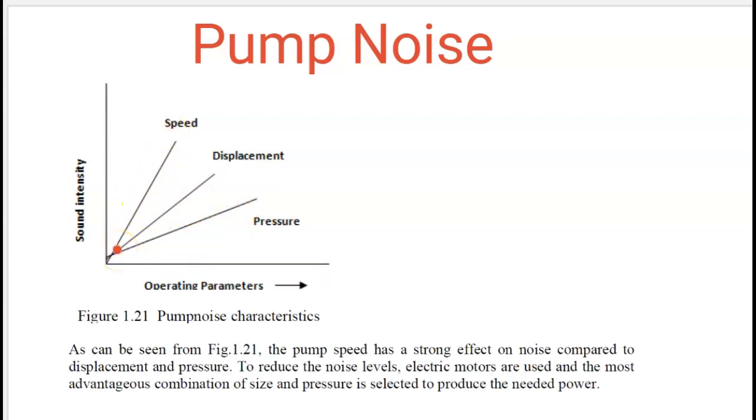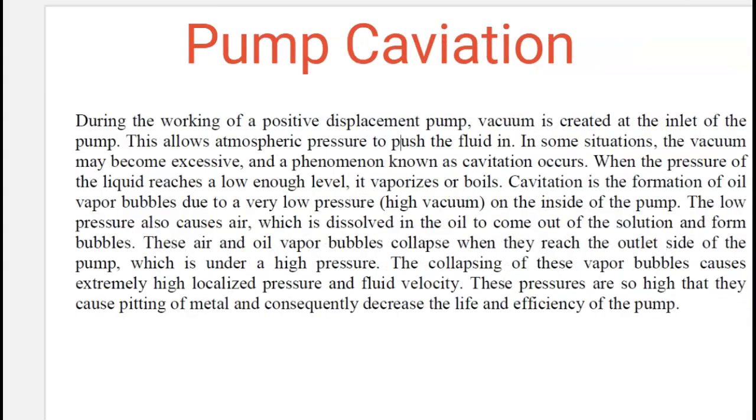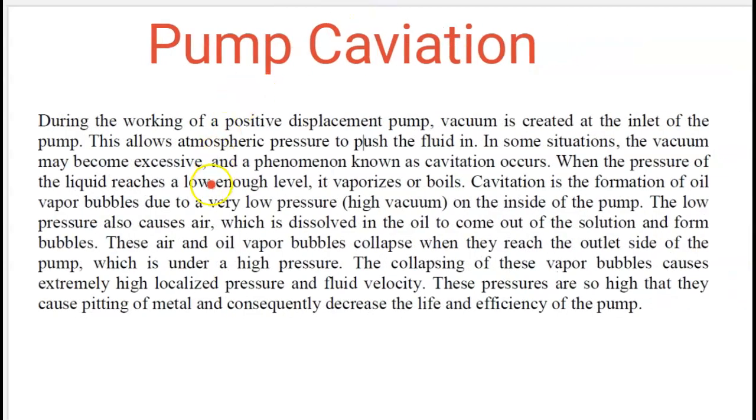If you are looking at the displacement, how much fluid you are displacing, as you increase the amount of fluid that you're displacing, the volumetric flow rate, the sound intensity increases. But speed is the one where the curve is quite steep, so a little bit of increase in speed will give you quite a high increase in the intensity. Okay. Now we have pump cavitation.